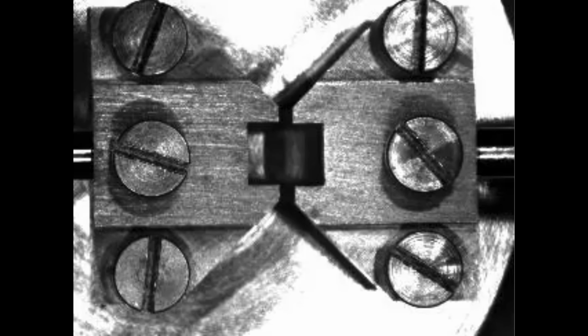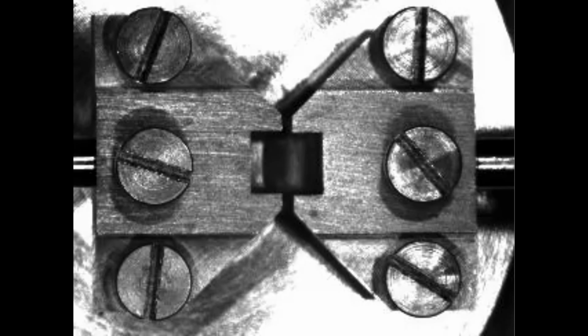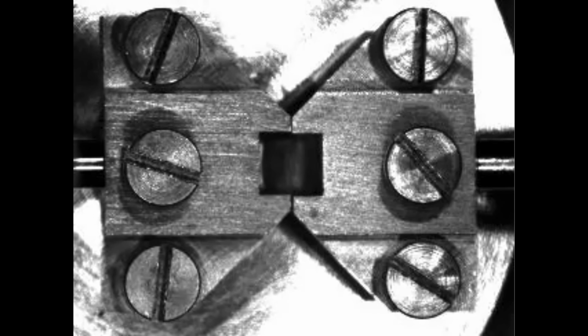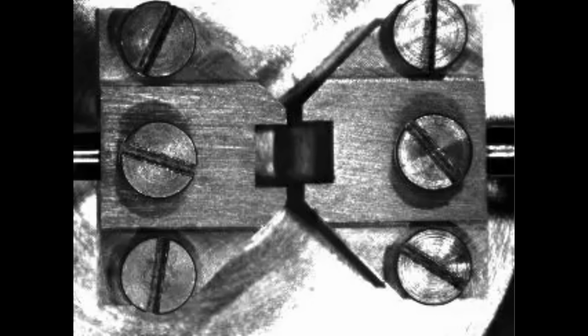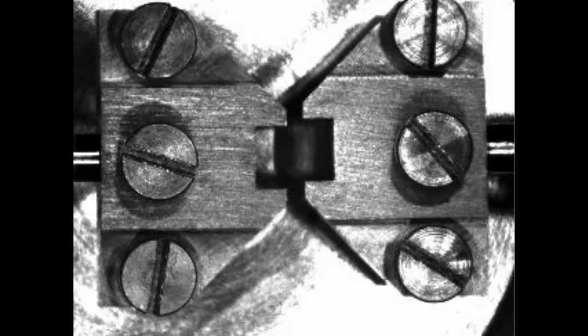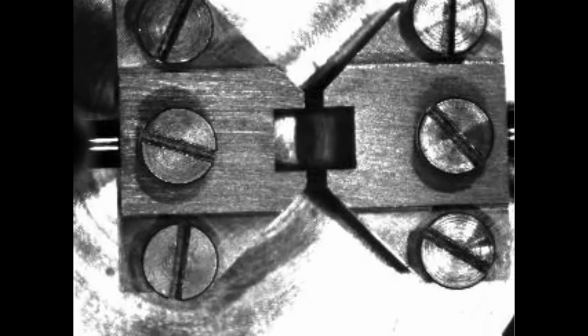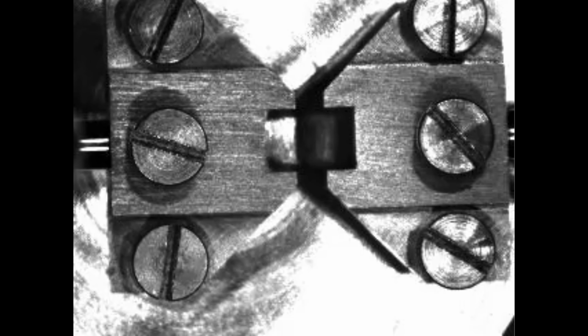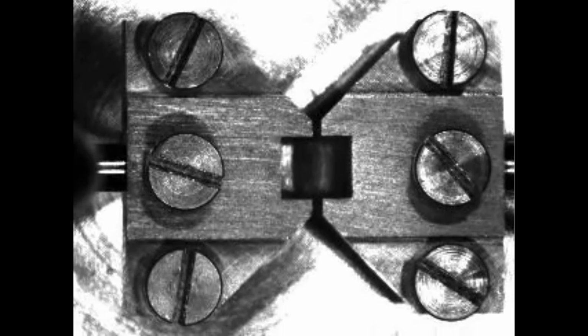Now gently move the jaws together and see how close your alignment is. We are still slightly off. We will make one more coarse adjustment. Although the jaws are aligned, you can see that the transducer side is higher than the positioner side. We will use 2 Allen keys to tighten the 2 back screws on the positioner side.